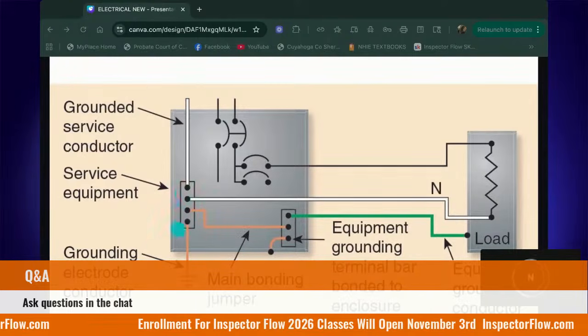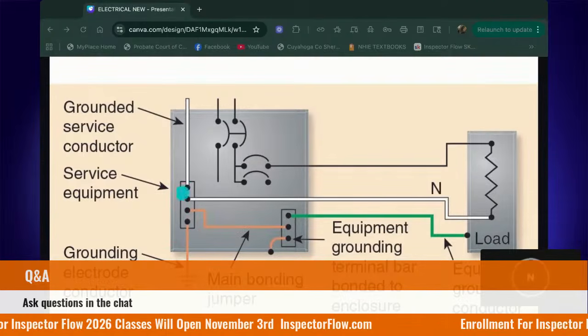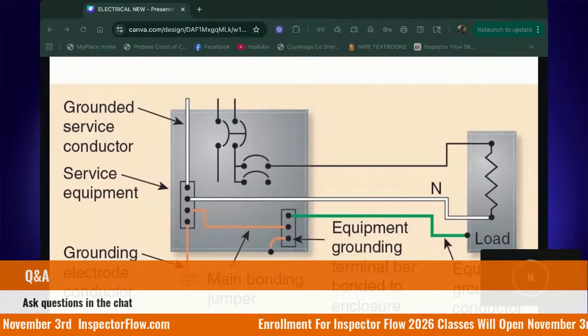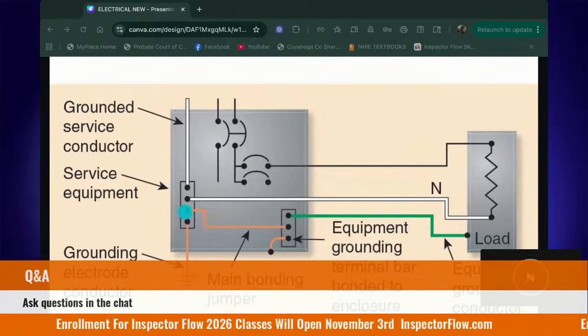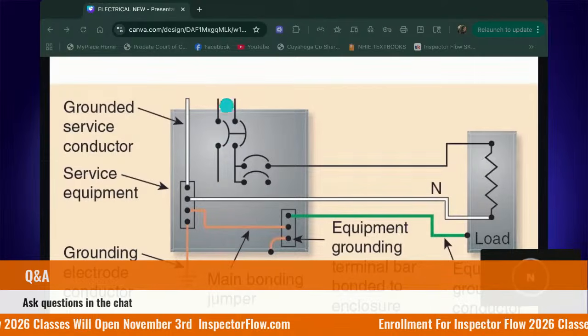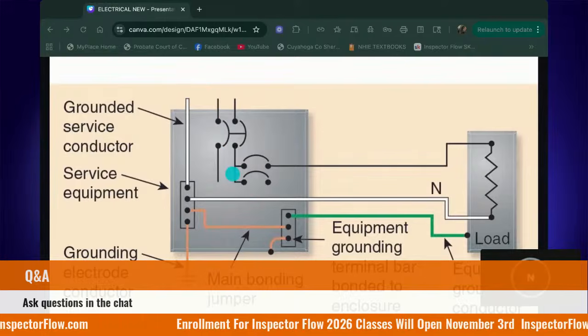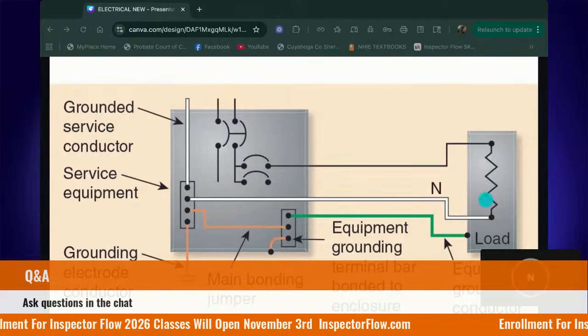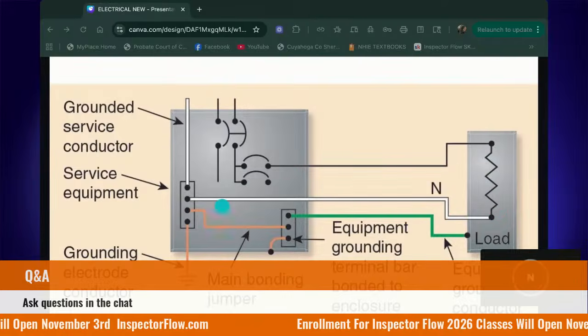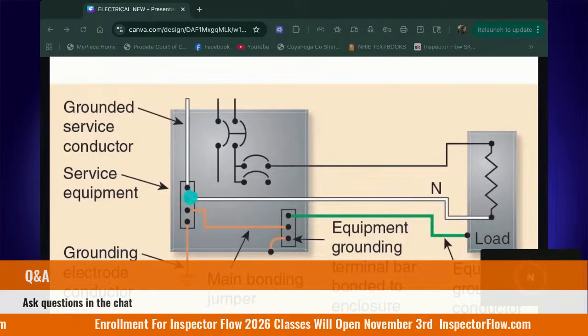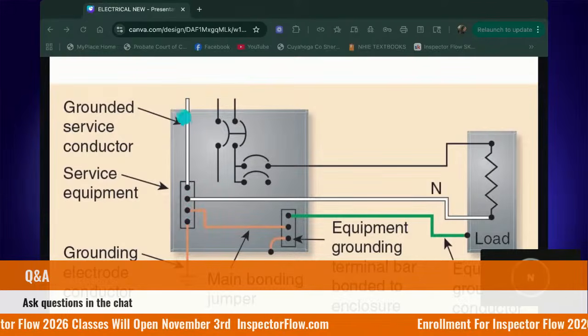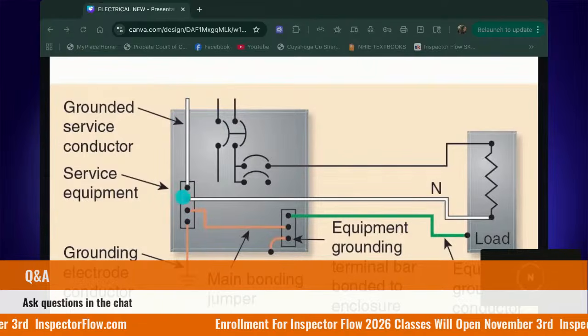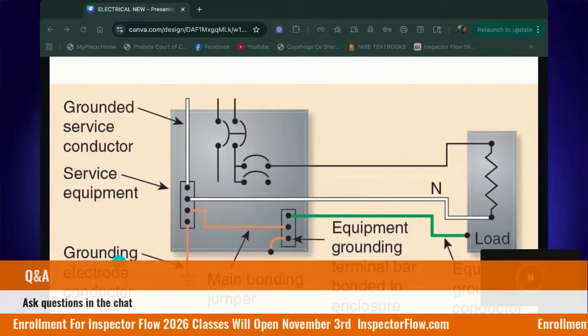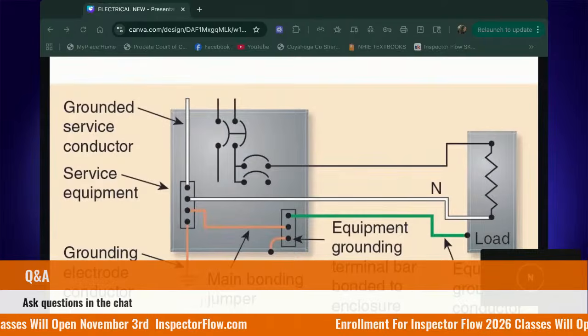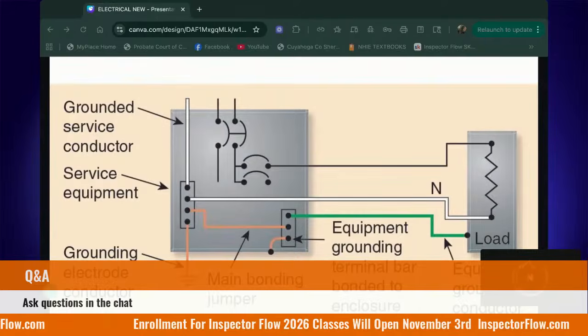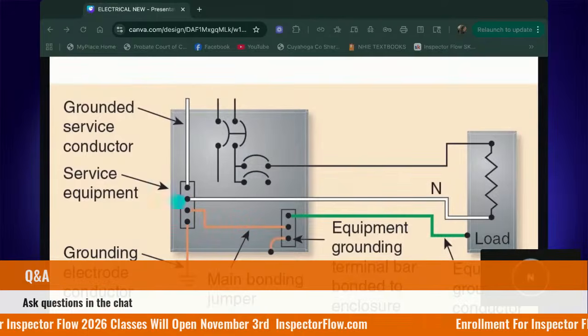During regular, normal operation, the neutral is the return path for the electricity that's flowing through the circuits. This is their way of showing the two mains coming in, these are breakers, it goes out, powers the load, it comes back via the neutral, terminates on the neutral bus bar by way of the grounded service conductor that's being dropped in, goes back to the source. That is the circuit. Make sense?